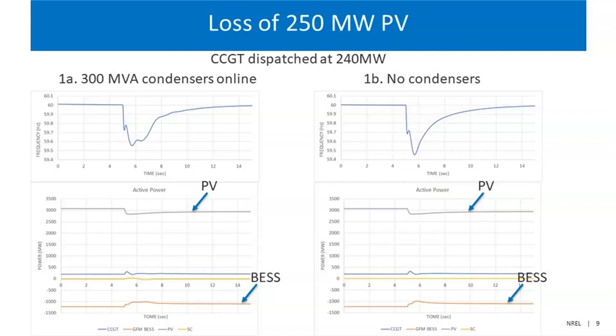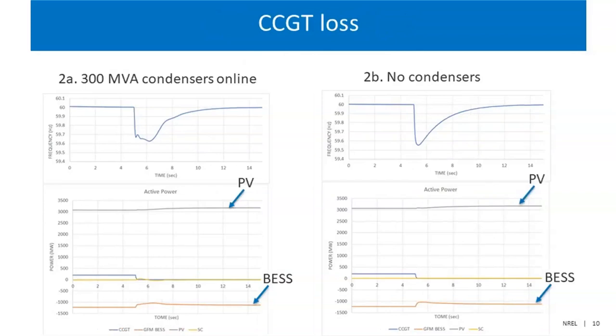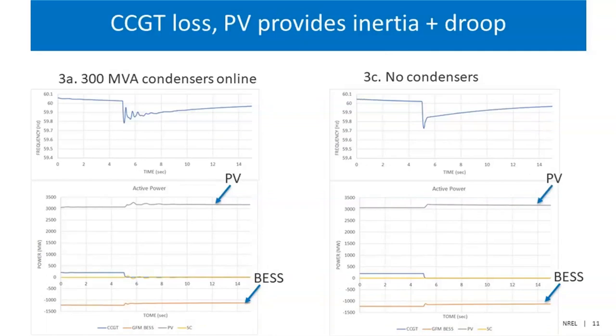We looked at the next case where we actually drop that last remaining piece of inertia in the system, and everything is essentially 100% inverter-based. And again, this was done with and without synchronous condensers, and you can see the system response. Again, the gain from synchronous condensers in terms of frequency response itself is not very significant. It could have been significant if you put more and more synchronous condensers and added inertia, but again, it all comes at a cost. And one interesting case is this one, when again, we dropped the last remaining combined cycle unit, and the PV plants that happen to have 5% headroom provide both inertia and droop control. And now you can see that all of a sudden the frequency response is significantly better than in the previous two cases. Frequency nadir is low, recovery is okay.